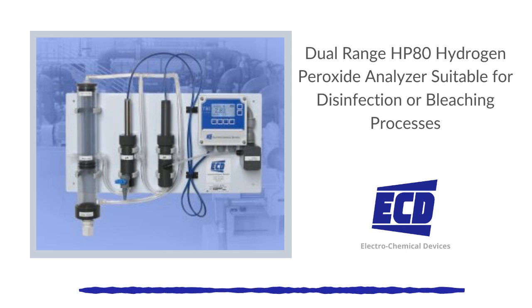The HP80's H2O2 sensors feature a measurement range of 0 to 200 parts per million, 2000 parts per million, 2%, 20% optional. The pH sensor has a range of 2 to 11 pH. Operating temperature range for these sensors is 0 to 45 degrees Celsius, 32 to 113 degrees Fahrenheit, with automatic temperature compensation for the H2O2 sensor.